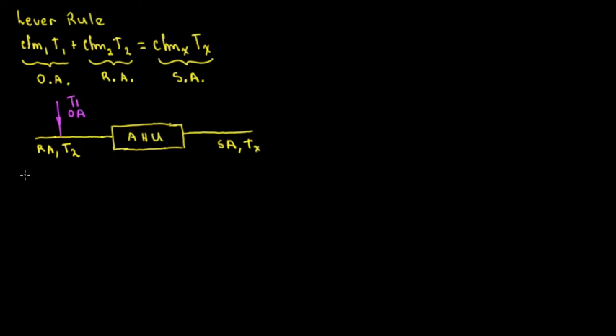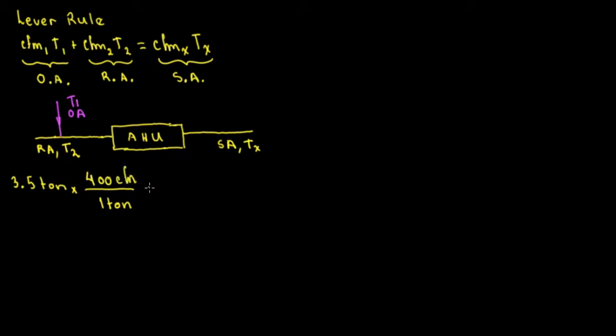Say that we have a 3.5-ton unit. What is the design CFM we need? As we know, we're going to use the rule of thumb which is 400 CFM per ton. So for a 3.5-ton unit, we're going to need 1,400 CFM. That's going to be the supply air — 1,400 CFM — and the return air is also going to be 1,400 CFM.